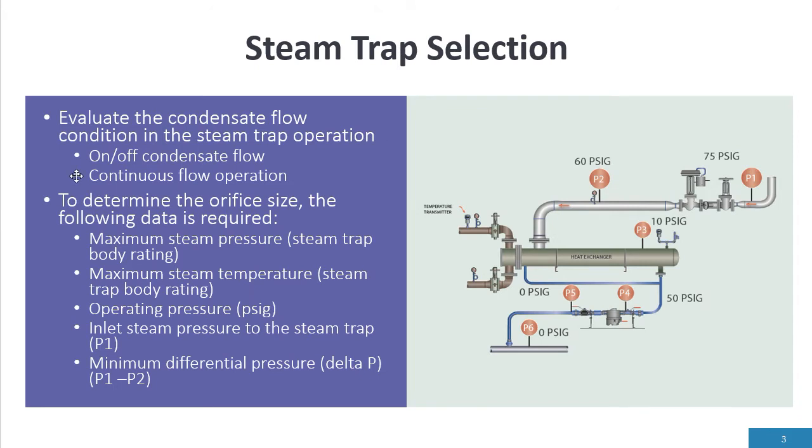Evaluate the condensate flow condition for the steam trap operation. We have two types of steam traps. No matter what steam trap is manufactured, there's two types: continuous flow and on-off operation. So if I have a heat exchanger with a modulating valve, that's going to be continuous flow to the process. I might want to go with a continuous flow type steam trap. The other operational design is on-off.